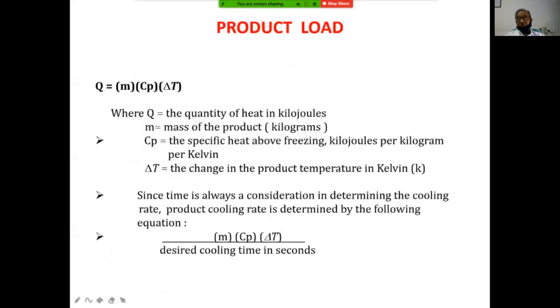Now, how to calculate the load? That is simple. There is a standard formula: mass into specific heat into temperature difference. That is the only formula we have to use for considering the load. So the requirement is mass into Cp into delta T. You divide that by the time in which you want to do the cooling, and you will get the cooling load, that is kilocalorie per hour or kilowatt, or BTU per hour, whatever system we use, that gives you the requirement of Q or the cooling load.